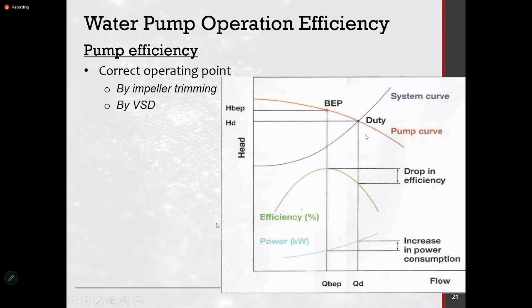All of them are drawn in one graph so that it is very easy to find. Ideally, your duty point should be as close as possible to the best efficiency point. If you can coincide, ideal, but very difficult to coincide. So you generally take a little bit of a higher capacity and target somewhere here without targeting the best efficiency point, because with time the friction losses will increase with the piping and system and you will start moving here. That is not a very good situation where the flow also will reduce. So you target somewhere here so that even later you are moving closer to the best efficiency point.